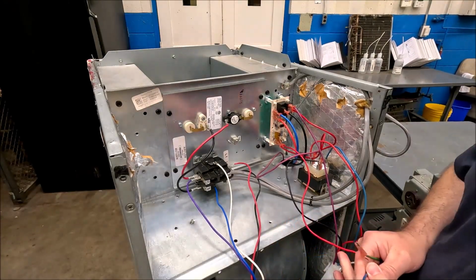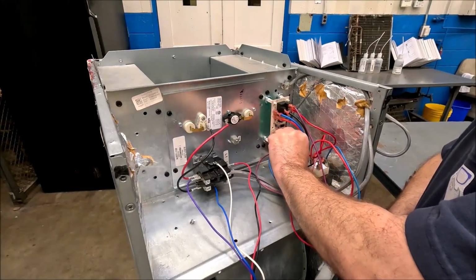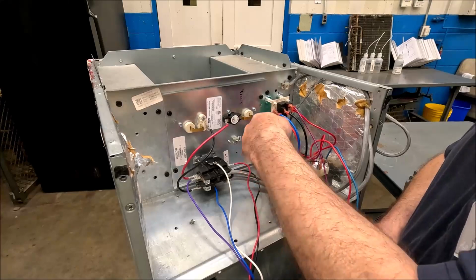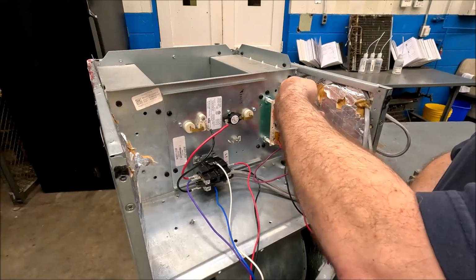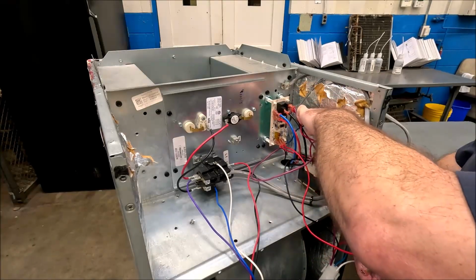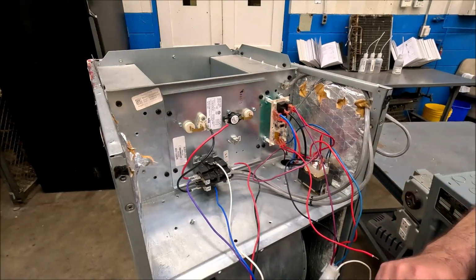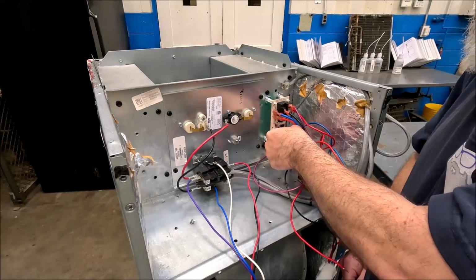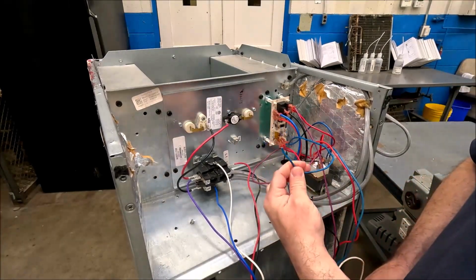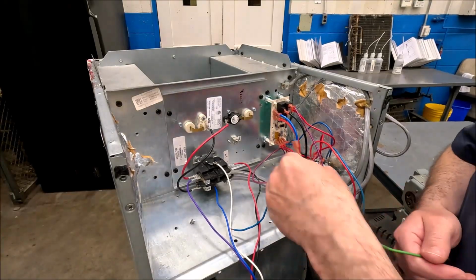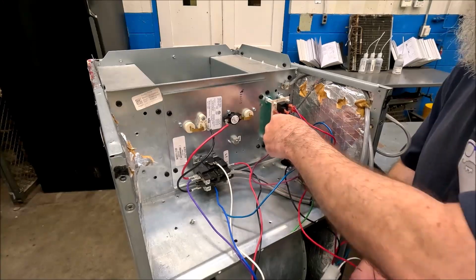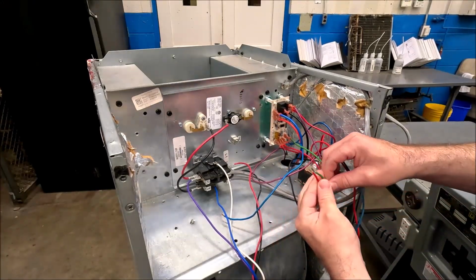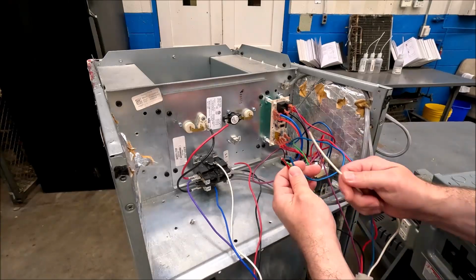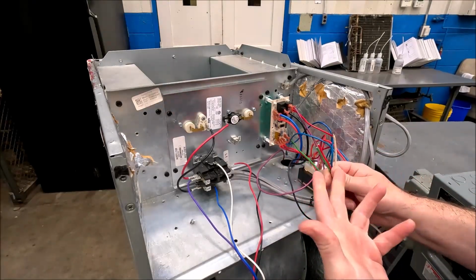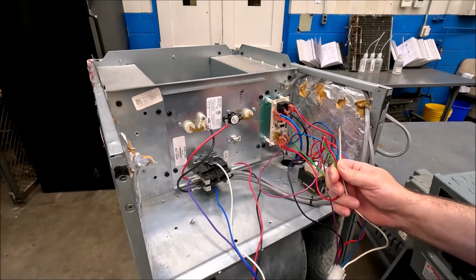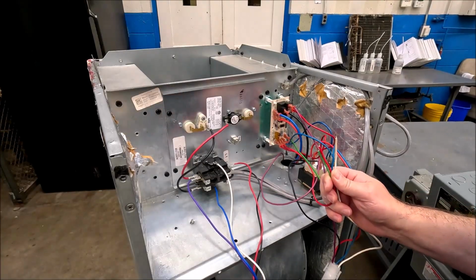So this transformer common right here, in terms of flow, it would come from the board, and I have a little buddy clip on the 24 common of this transformer, and it's right there. So transformer common is done. Now we have a regular common, and that's my wire connection there, and I have a regular G. So to wire this thing up off of the wiring diagram is not that hard, and you wind up with a couple loose ends, and this will be your air handler connections and a wire nut and stuff to your field wiring, to your thermostat and your heat pump or air conditioner, whatever you have.